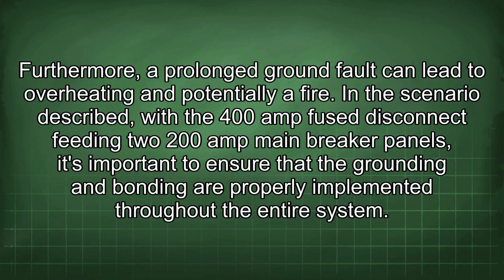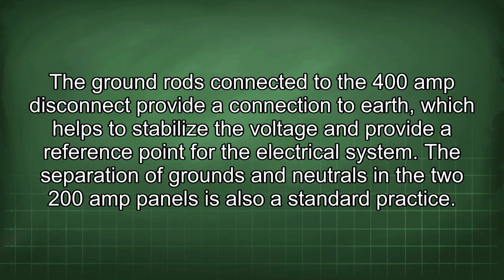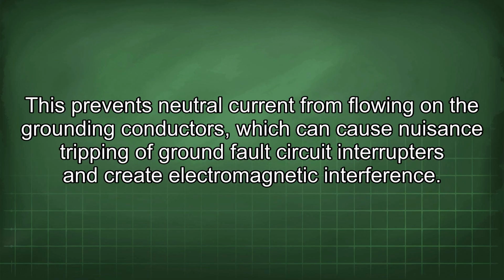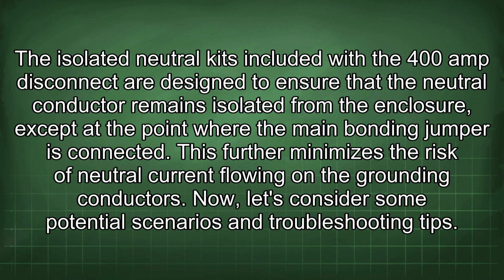In the scenario described, with the 400 amp fused disconnect feeding two 200 amp main breaker panels, it's important to ensure that the grounding and bonding are properly implemented throughout the entire system. The ground rods connected to the 400 amp disconnect provide a connection to earth, which helps to stabilize the voltage and provide a reference point for the electrical system. The separation of grounds and neutrals in the two 200 amp panels is also a standard practice. This prevents neutral current from flowing on the grounding conductors, which can cause nuisance tripping of ground fault circuit interrupters and create electromagnetic interference. The isolated neutral kits included with the 400 amp disconnect are designed to ensure that the neutral conductor remains isolated from the enclosure, except at the point where the main bonding jumper is connected. This further minimizes the risk of neutral current flowing on the grounding conductors.